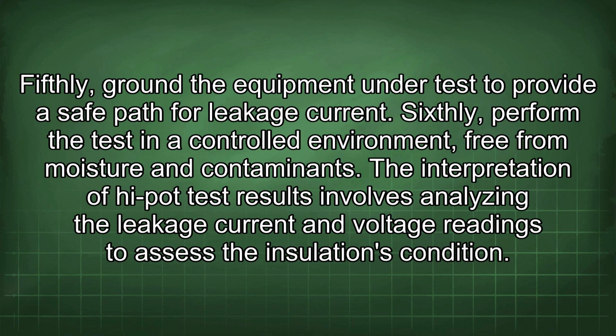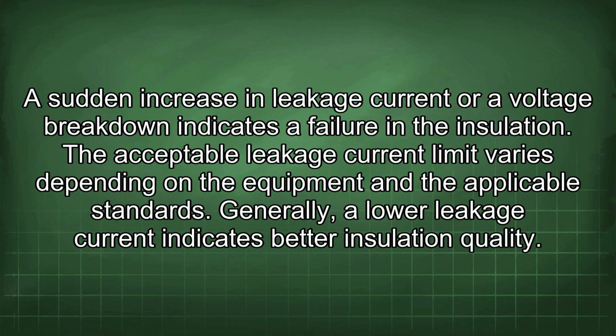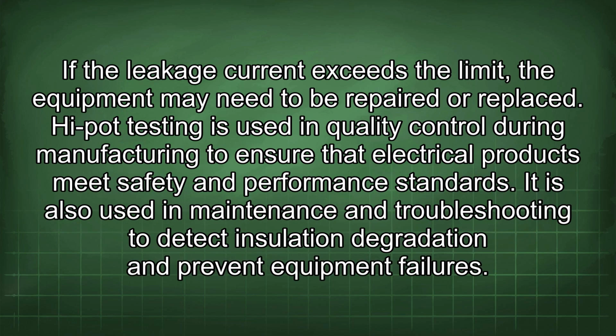The interpretation of hi-pot test results involves analyzing the leakage current and voltage readings to assess the insulation's condition. A sudden increase in leakage current or a voltage breakdown indicates a failure in the insulation. The acceptable leakage current limit varies depending on the equipment and the applicable standards. Generally, a lower leakage current indicates better insulation quality. If the leakage current exceeds the limit, the equipment may need to be repaired or replaced.